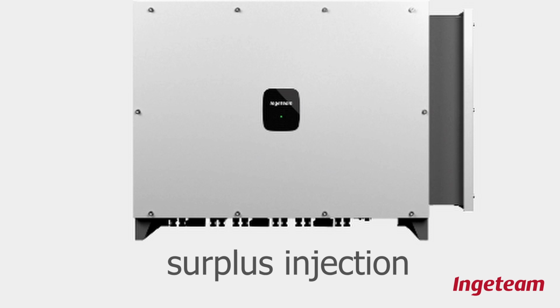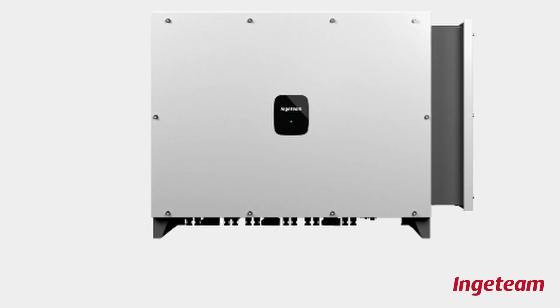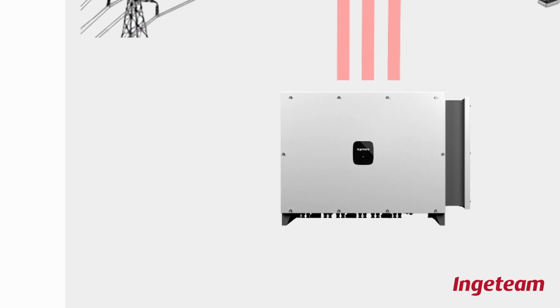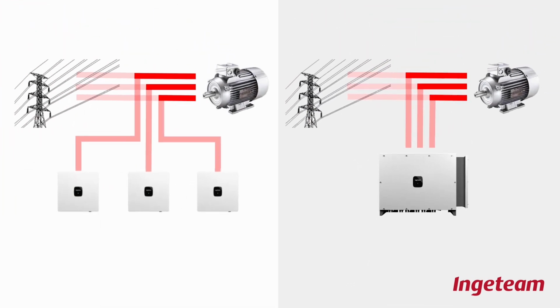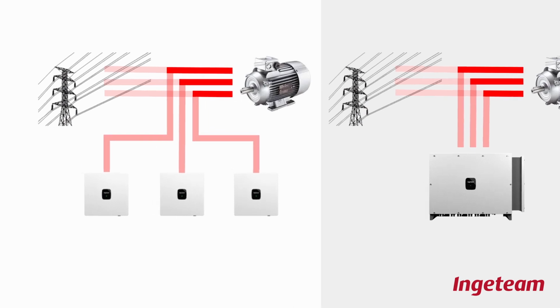In the case of systems that can inject power to the grid, three-phase inverters are more recommended because the inverters will always work at the maximum power point regardless of the consumption that is happening in each of the three phases. However, in the case of systems with zero injection, it is necessary to regulate the power generated in each of the phases in order to adjust it to the instantaneous consumption. Therefore, both options, single-phase and three-phase inverters, present advantages and disadvantages.